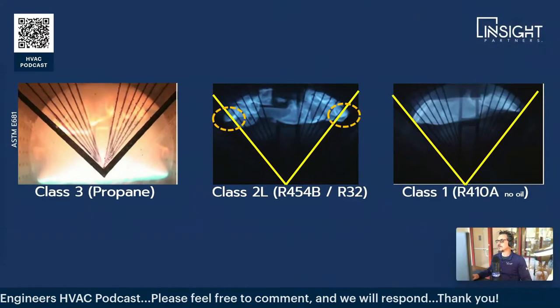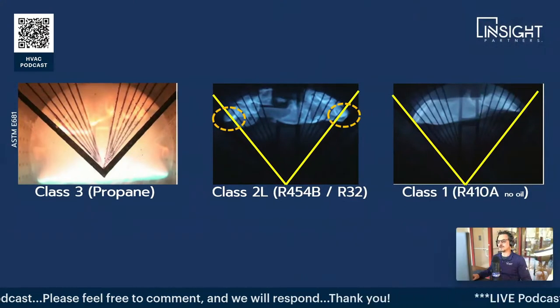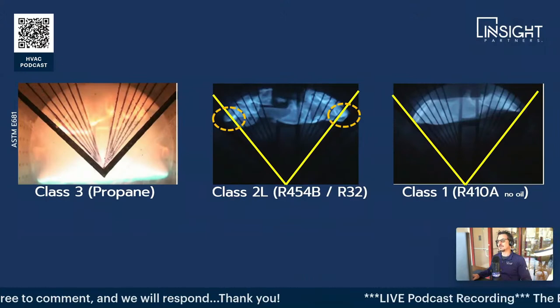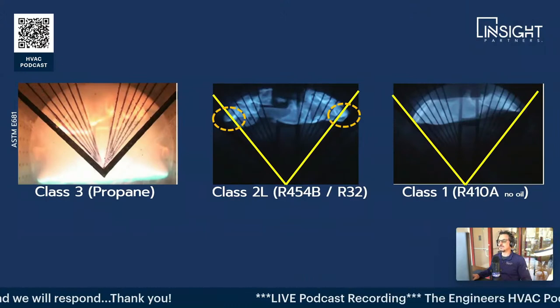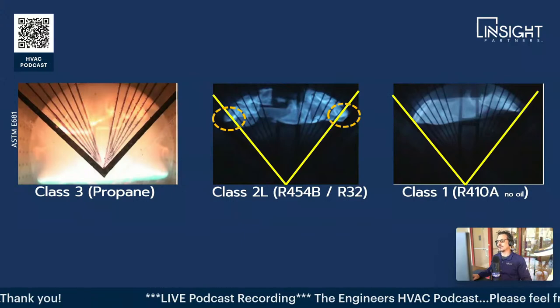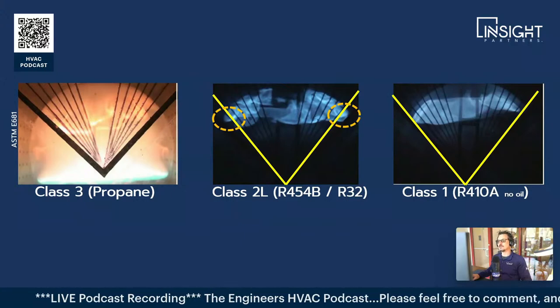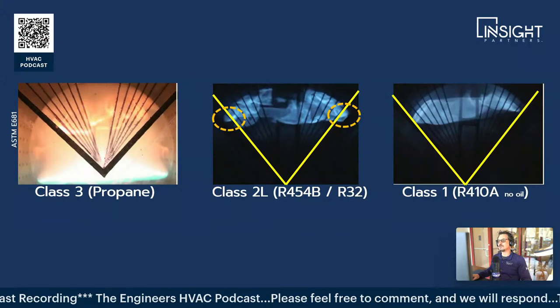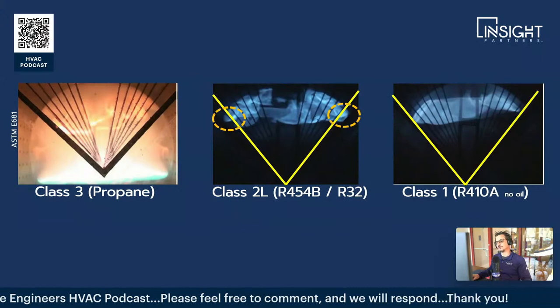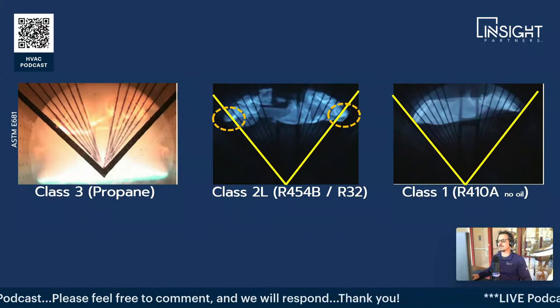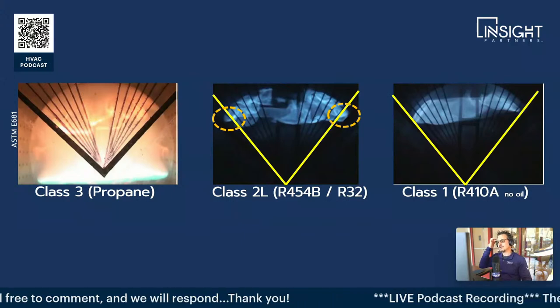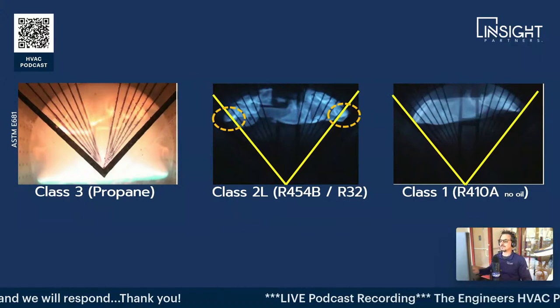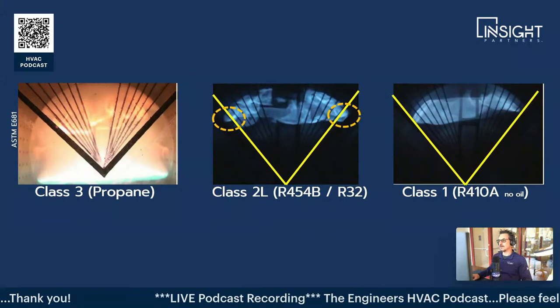I'm going to make this screen a little bigger here, and I'll leave these up for a second. So you can see that the difference between the class 1 and class 2L, or the A1 and A2Ls, is just a few degrees. The A2Ls, such as 454B and 32, have far less ignition energy than the A3s. Toasters, electric ovens, and other common household products will not ignite the A2Ls.